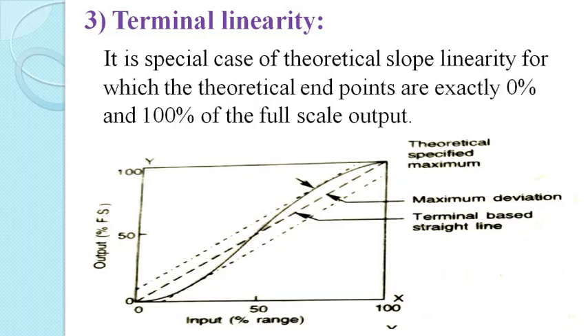The third type of linearity is terminal linearity. This is a special case of theoretical slope linearity for which the theoretical endpoints are exactly 0% and 100% of the full scale output. Here we draw the straight line such that the deviation on both sides of the calibration cycle is identical, which is known as the terminal based straight line. The following figure shows the terminal linearity relation.